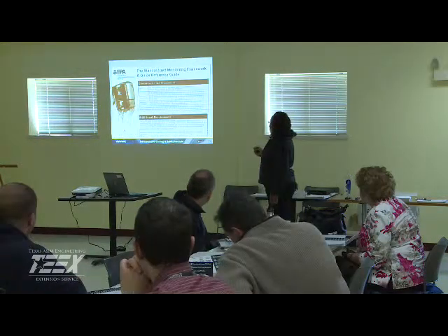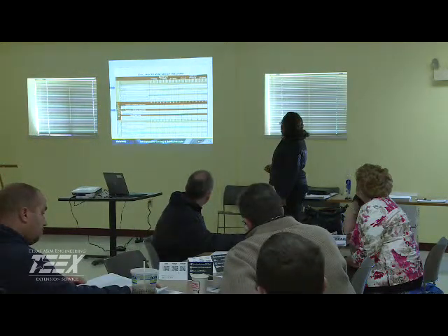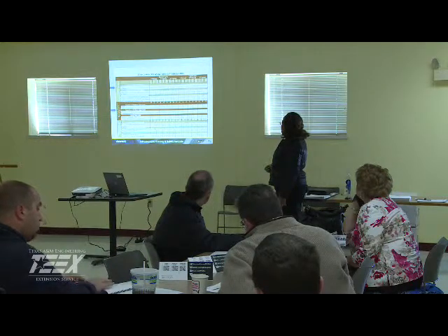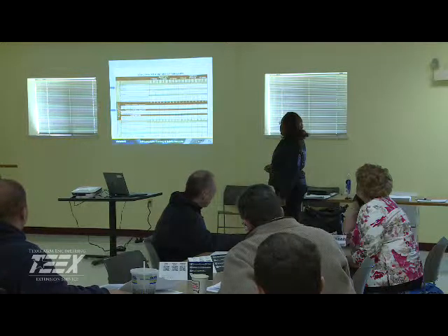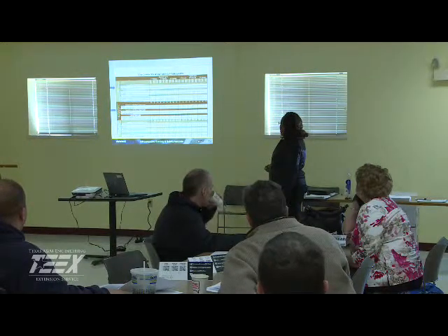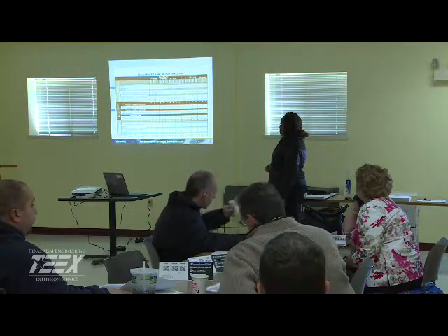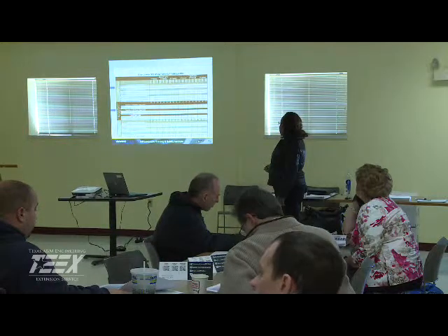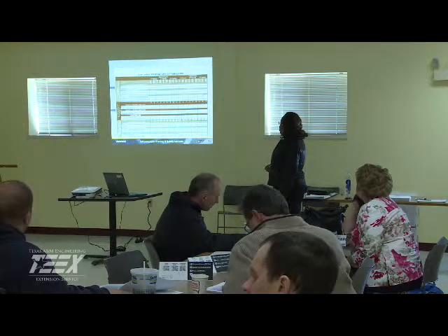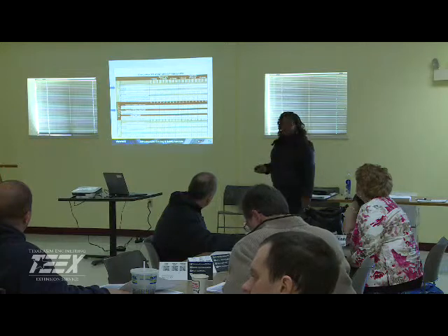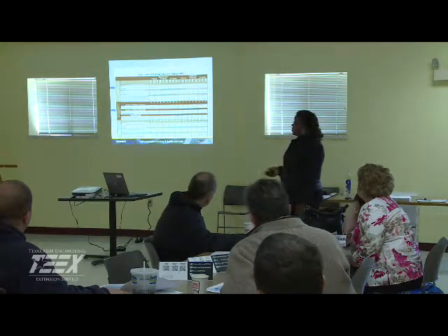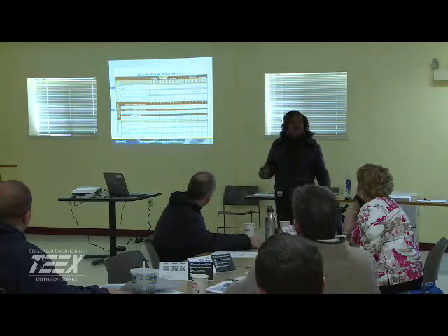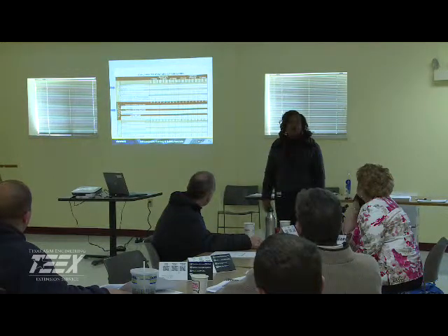For the volatile ones, there's the groundwater system, but you are a surface water system, so we'll look at that one. Surface water system below the trigger level, no sampling is necessary. With no waiver, but there may be some detection, you're looking at an annual basis. So again, a quick reference guide. This reference guide takes you all the way to the year 2019, so there's no question, what do I need to monitor?